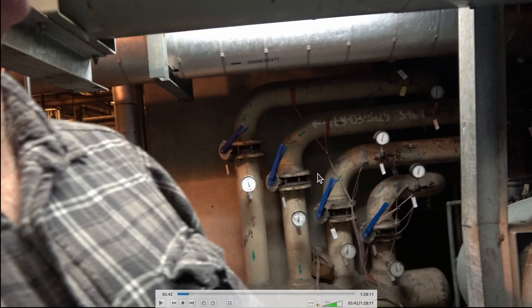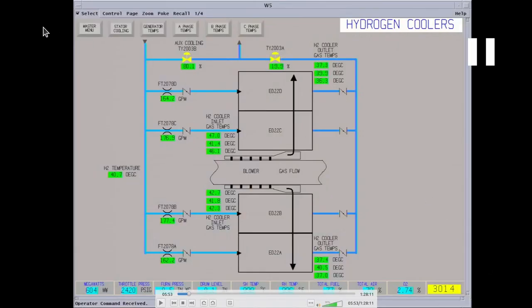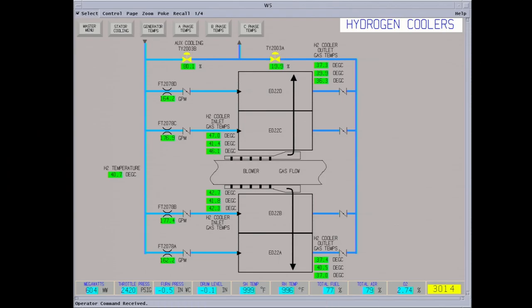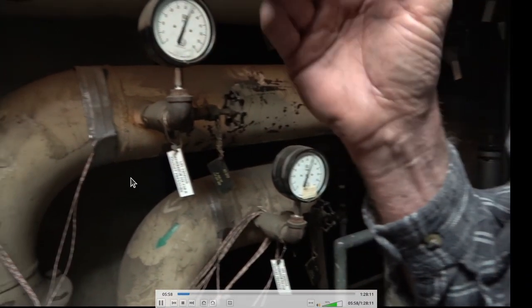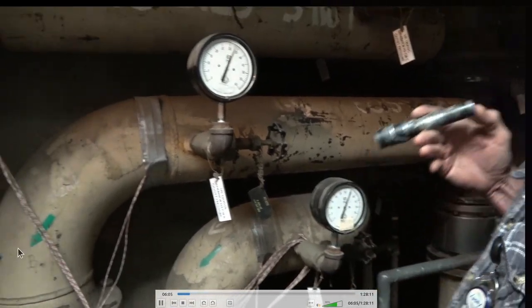These are the generator cooling lines — this is the cooling water for the hydrogen in the generator, mostly for cooling the rotor. These are the isophase bus ducts. Down at the bottom is your main power coming out. This is your generator hydrogen cooler — it cools the hydrogen in the generator using aux cooling water. It's pretty much for rotor cooling, as the stator is water cooled on a separate system. You have butterfly valves to set the flow on it, and some drain lines to make sure nothing is leaking in the coolers inside.